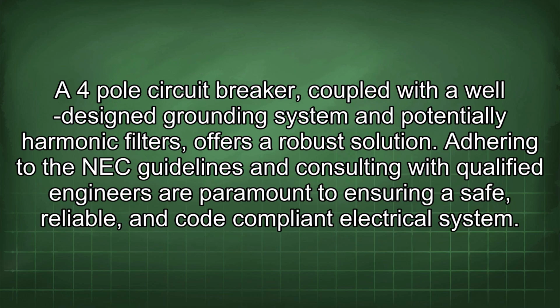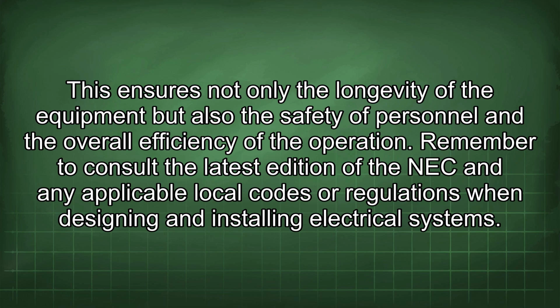A 4-pole circuit breaker, coupled with a well-designed grounding system and potentially harmonic filters, offers a robust solution. Adhering to the NEC guidelines and consulting with qualified engineers are paramount to ensuring a safe, reliable, and code-compliant electrical system. This ensures not only the longevity of the equipment, but also the safety of personnel and the overall efficiency of the operation. Remember to consult the latest edition of the NEC and any applicable local codes or regulations when designing and installing electrical systems.